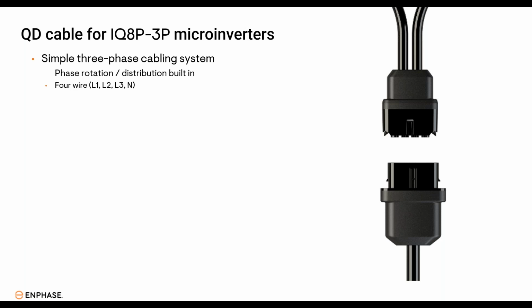The QD cable is the 4-wire 3-phase AC bus that collects all the microinverter output and sends it to your sub-panel board. If you're familiar with the residential, this is essentially the same cable as the Q cable that the residential microinverters connect to. Obviously, the only difference is that this is a 4-wire cable. It has phase rotation built in, so you don't have to worry about that as much. It takes a lot of the guesswork out of it, and you don't really have to understand what phase rotation is as much.